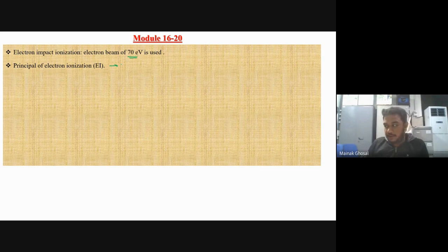When the fragment goes, it will show you some mass by charge ratio. And actually, there is no balance. As Professor Raman has also told you, don't think that there is some balance inside that measures the weight and tells you the weight by charge. There is nothing like that. You have seen that there is a correlation between m by z and the voltage. So it actually measures the voltage and the distance through which the ion has traveled, and from there it is converted to the m by z ratio using the relation that was discussed. It is not measuring your actual mass, it is just converting the result into the m by z ratio.